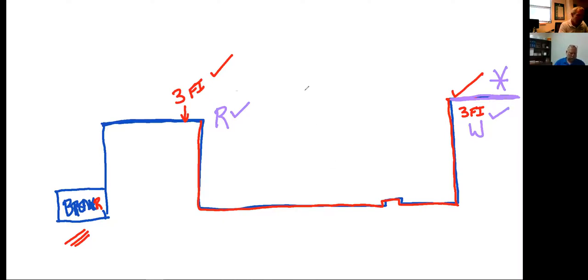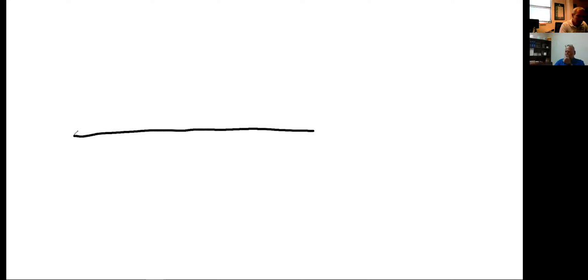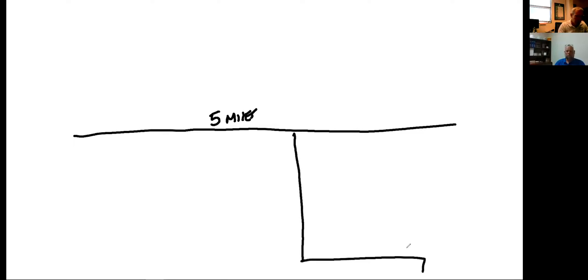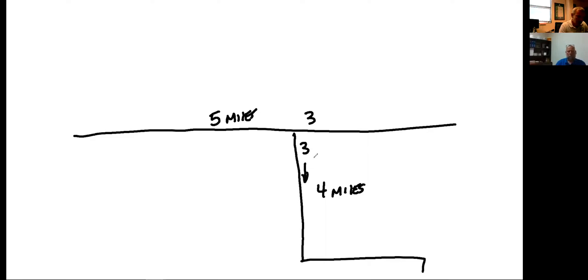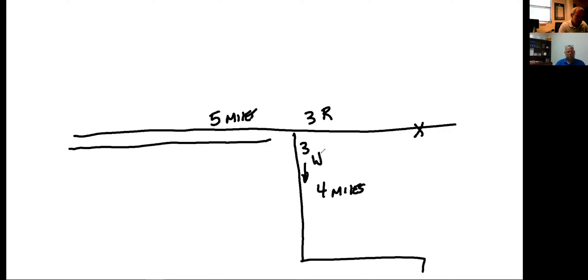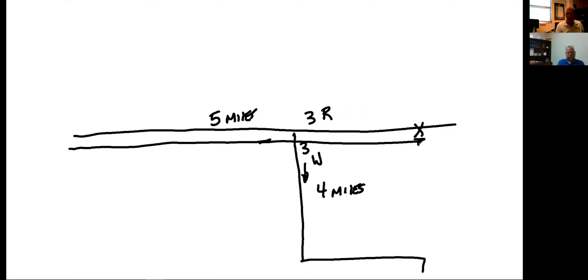If you've got an underground feeder that goes for five miles and you've got another piece of the feeder that comes down here and goes another four miles, it would be a great opportunity to put three indicators here and three indicators going in this direction. I'm driving down here, the fault occurred here, these are going to be red, these going the other direction are going to be white — no fault happened down there. So now I can keep patrolling in this direction until I find the fault. I like to call it like a little sectionalizer — it sectionalizes what you need to patrol.